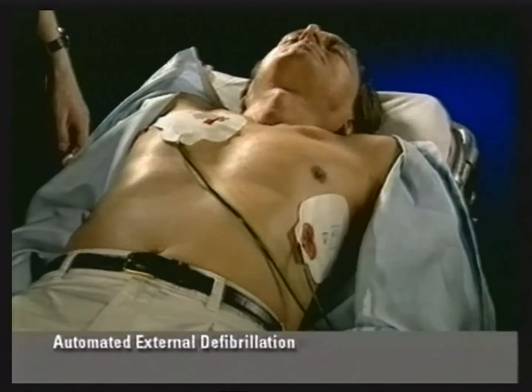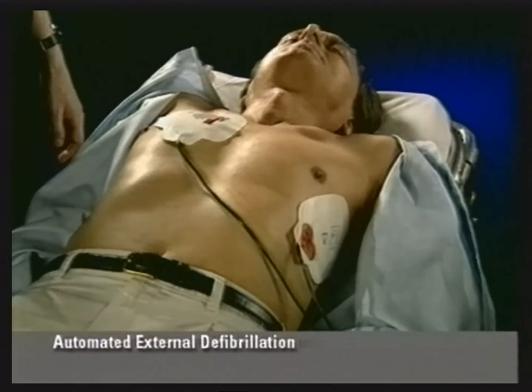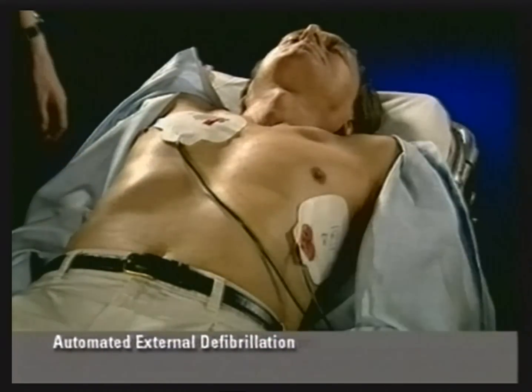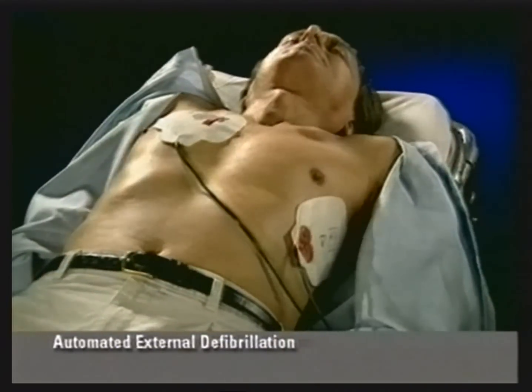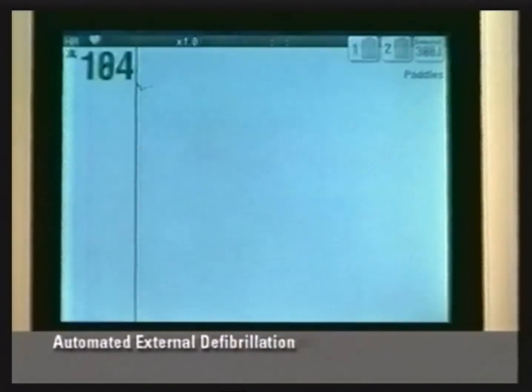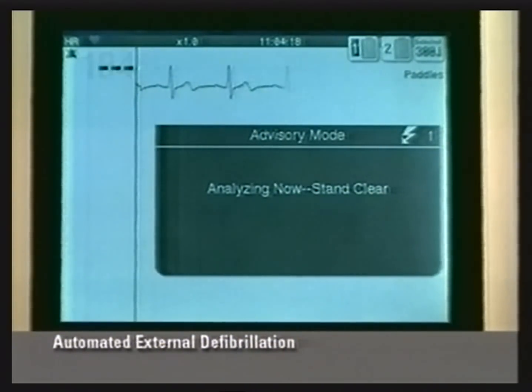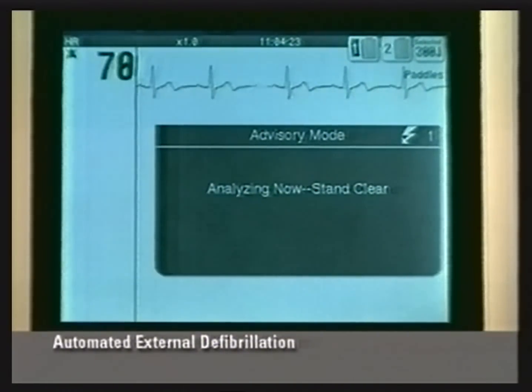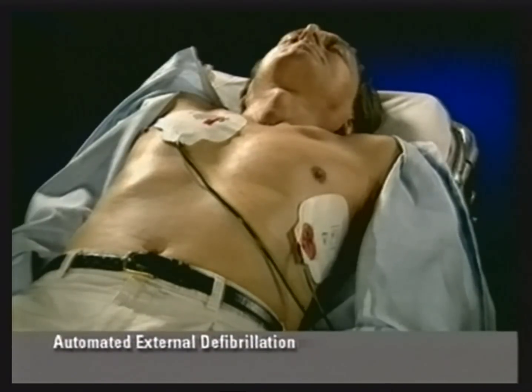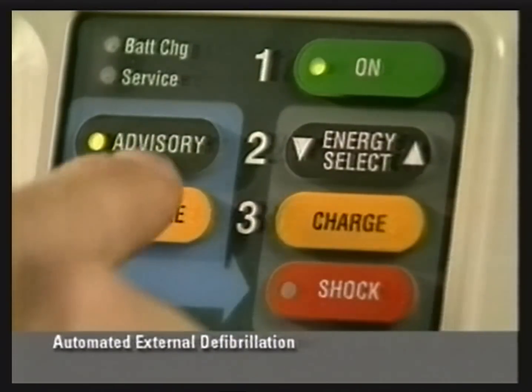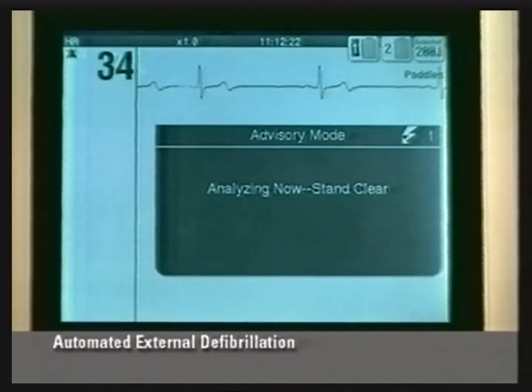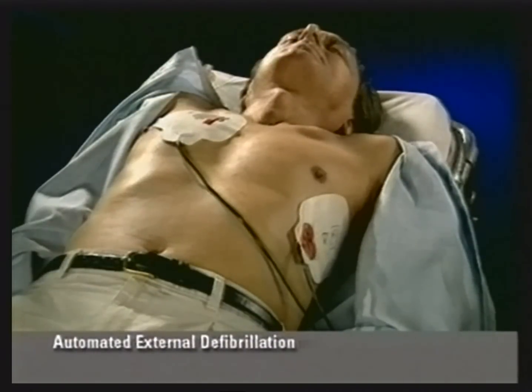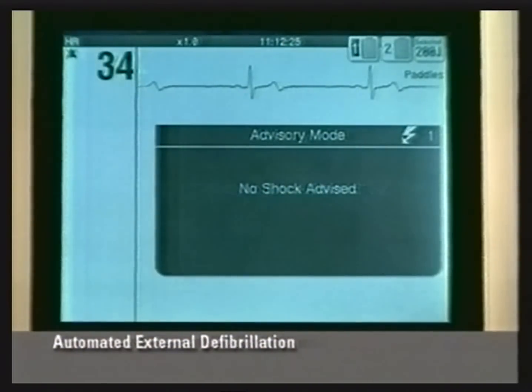Tell everyone to stand clear from the patient. Check that no one is touching the patient, then push the shock button to discharge the energy to the patient. If auto-analyze is on, the defibrillator automatically analyzes the rhythm after the shock. If the auto-analyze feature is off, you are prompted to push Analyze. Analyzing now.